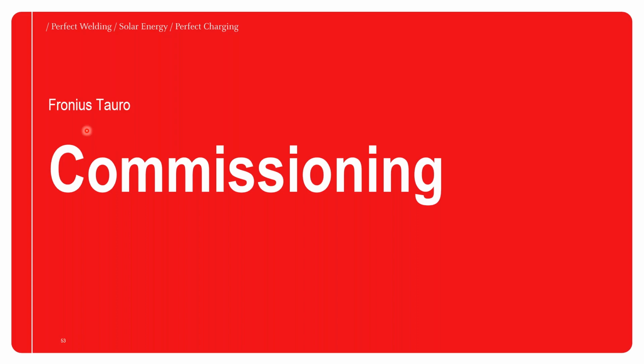And as we might have known, the Tauro doesn't come with a display, just as is the case with the Gen 24, as we discussed in our previous webinar. So it means that we will be commissioning it with a monitoring or commissioning device, as you would put it, and then of course with a communication gateway. And this communication gateway is what we call the pilot, as in the case of the Gen 24.